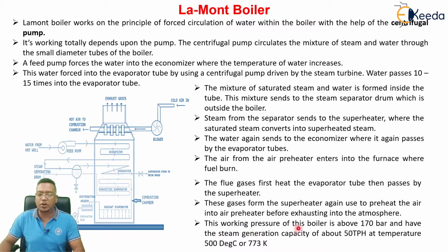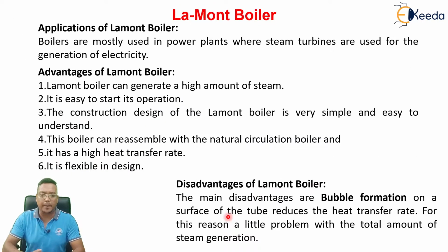The working pressure of this boiler is about 170 bar, and it has a steam generation capacity of about 50 TPH at a temperature of 500 degrees Celsius. So the Lamont boiler is a very high pressure boiler and steam generation is very high, that is 50 TPH. So friends, this is all about the Lamont boiler. Now let's see the application, advantages and disadvantages of the Lamont boiler.